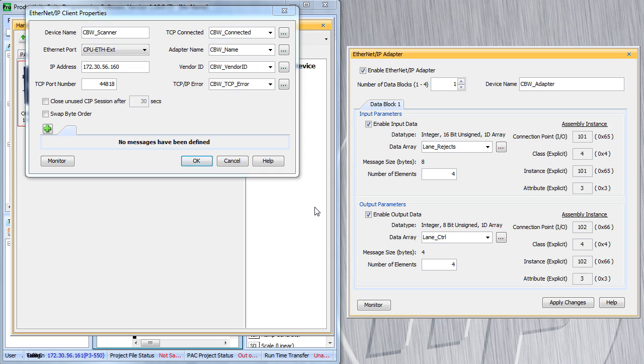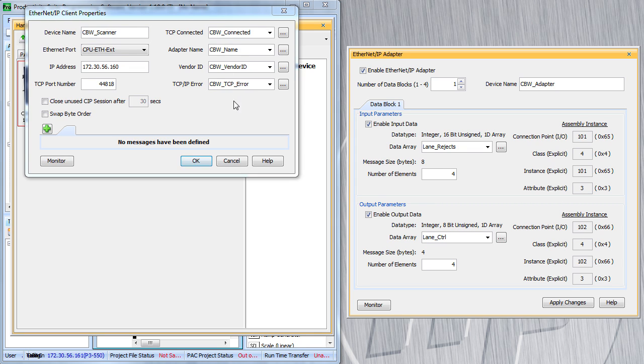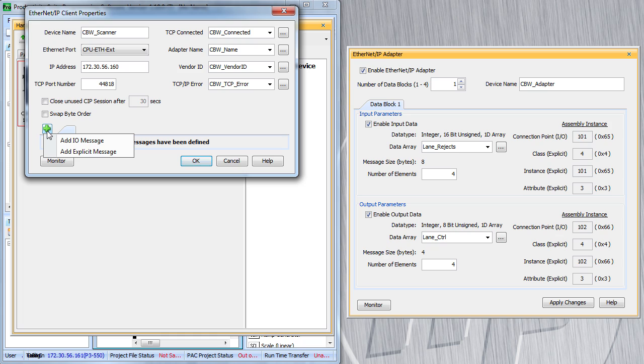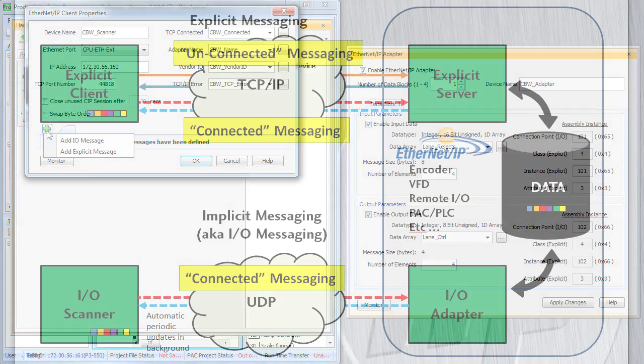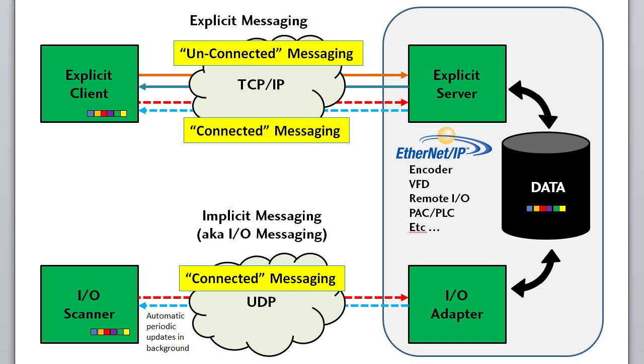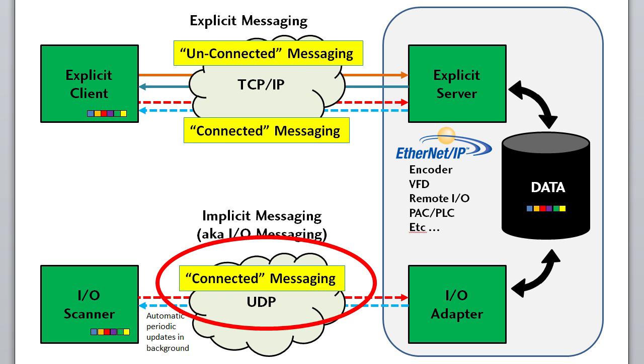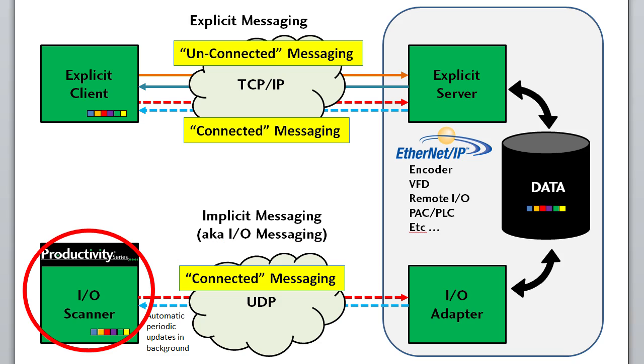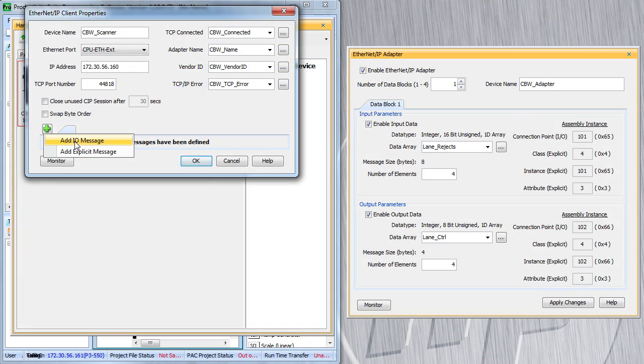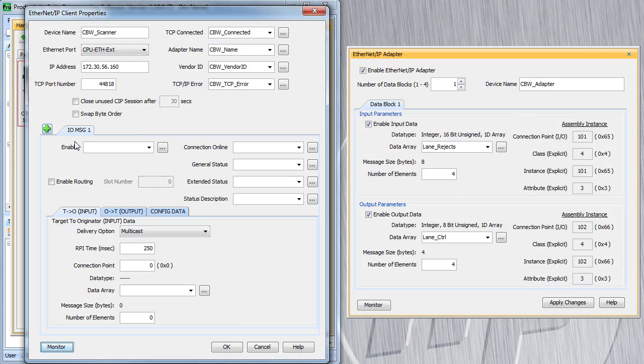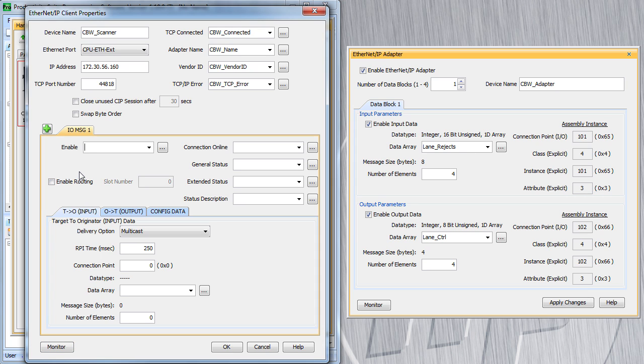I've rearranged the screen here a little bit so we can see the adapter and the scanner dialogs at the same time because we are going to need some of these parameters over here in the scanner dialog. So far we have given it a name and an IP address and created some tags so we can monitor the status of the connection with the adapter. This plus sign is where we choose the type of connected messaging we want. In the overview video, we said we can do connected messaging via explicit TCP IP or implicit UDP. In this video, we are setting up a scanner to do implicit UDP so we will choose that one. And now we have a few more blanks to fill in to set up that connection. The enable – this is a bit that you will set in your ladder logic to enable the scanner. So we will call that CBW enable.